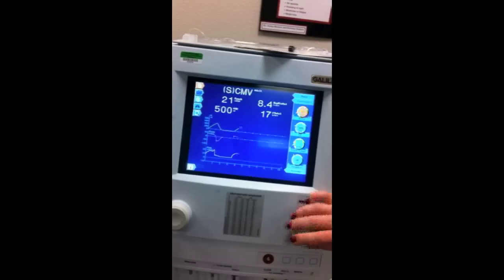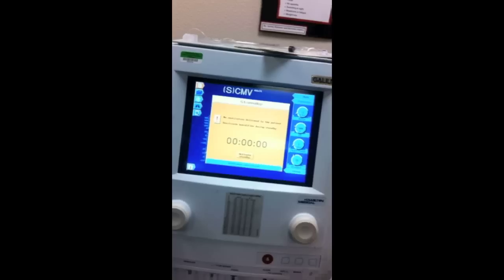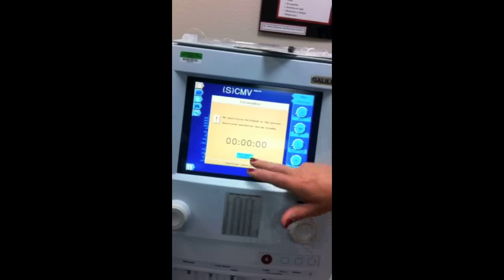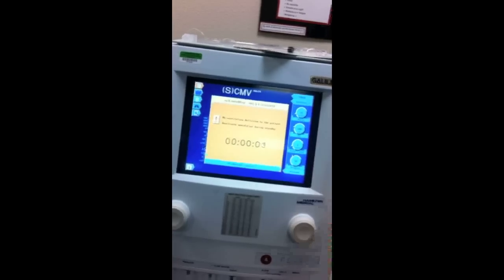Okay, so the other thing from the mode that you can do is put it into standby, which is right here. Standby, orange, hit confirm. This is not in standby yet. You actually have to take it, and this is the time you're going to have to use the blue. Activate standby, confirm, now it's actually activated. Until you do that, it's not actually in standby. And it'll tell you how long it's been in standby. So now we're done.